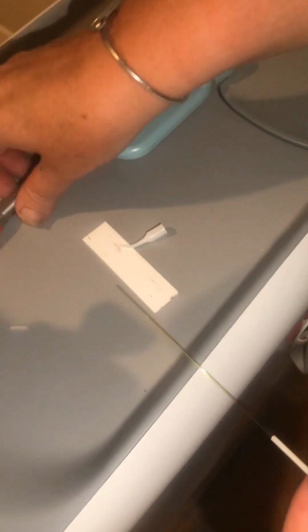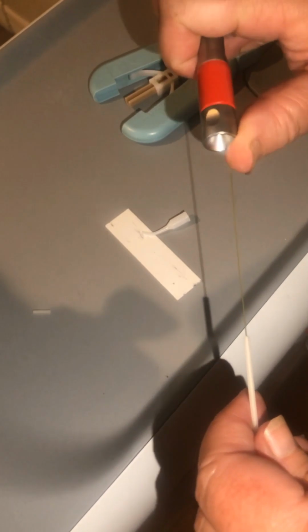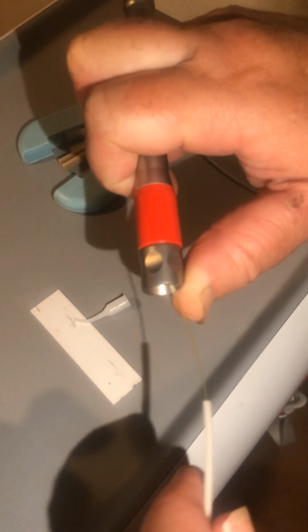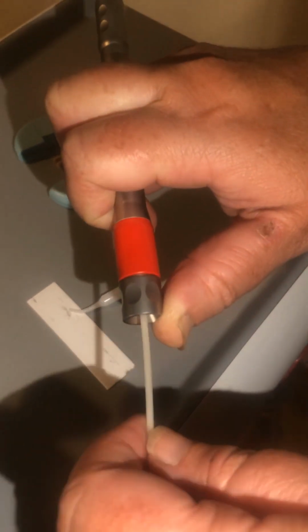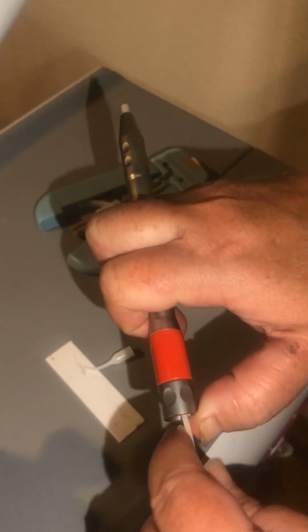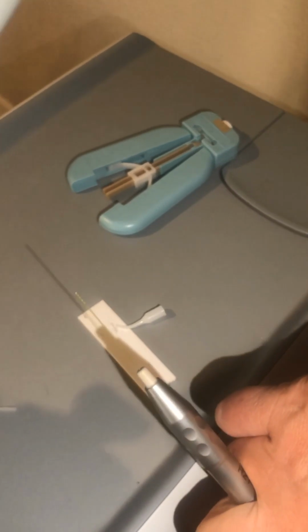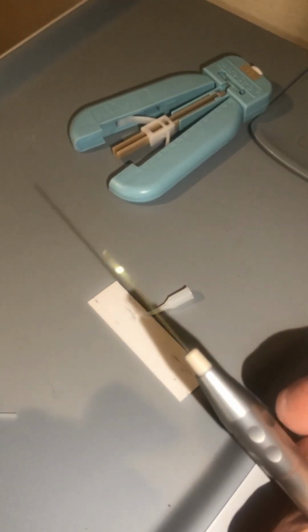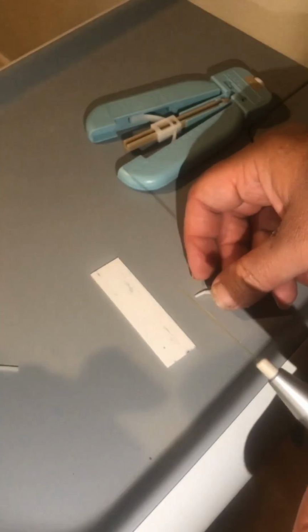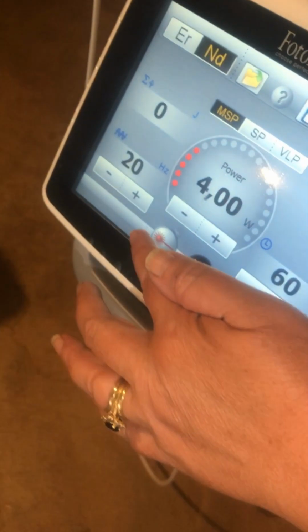And then now we can actually feed that through the end of the R21 handpiece. We're gonna push up on that end part so that we can feed it through, release that lock, and let it come out the other end. You wanna have about that much of the fiber out the other end so that we can load this tip on the end of it, okay? But I'm gonna show you this here in a second. What we wanna do first, before we go to put that tip on, is we wanna check our aiming beam and make sure that we don't have any loss of energy. So I'm gonna activate the laser just to show me the aiming beam.